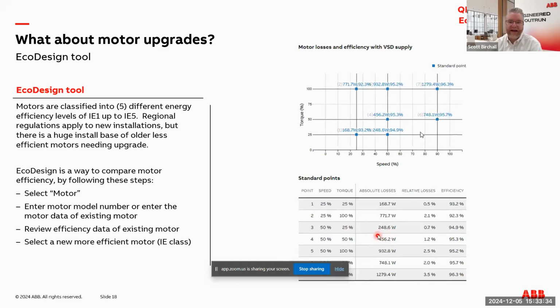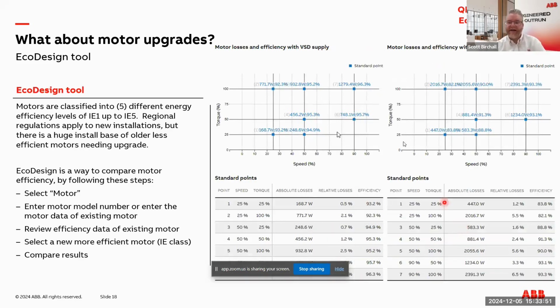Now if I want to look at doing this with a more efficient motor, I can do that same exercise where I select the motor. And now my more efficient motor I can see is 96.3% efficient, and at that half flow point, it's 94.9. If I put those two side by side, I can do some rough math on how much energy I would save by simply upgrading the motor, not even talking about the drive.